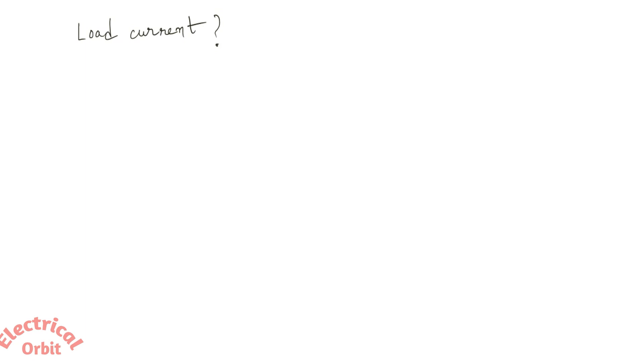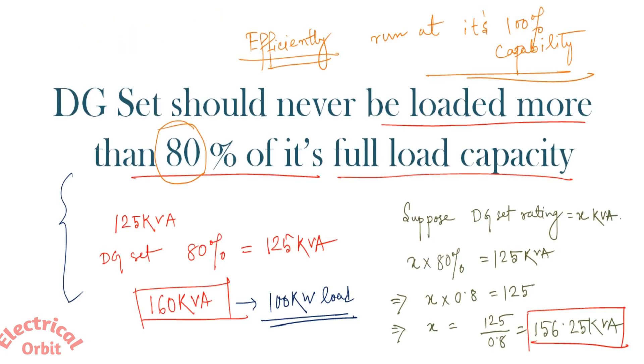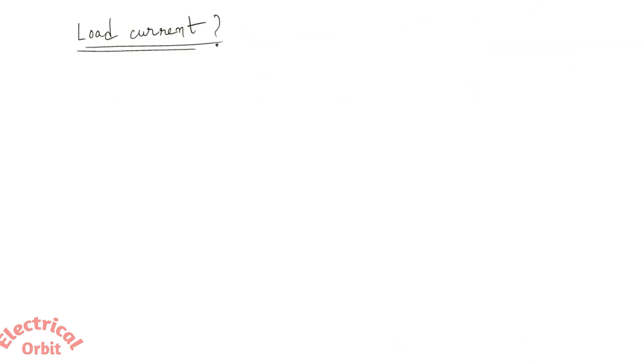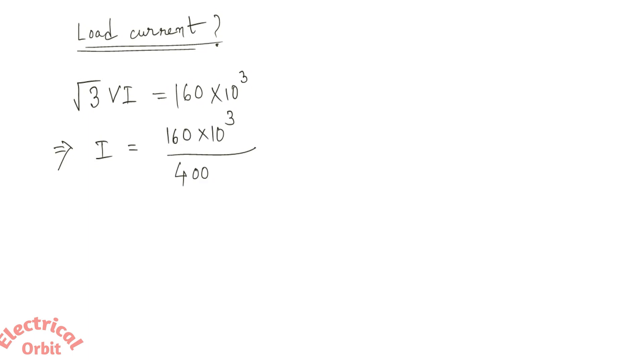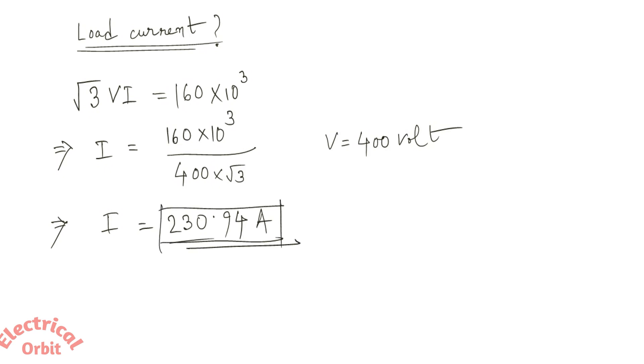Another question is: what about the load current of the DG set? Sometimes the load current capability needs to be determined. Since the total power is 160 KVA and this is a three-phase system, using the formula: KVA = √3 × V × I, we get I = 160,000 ÷ (√3 × 400) = 230.94 amperes.